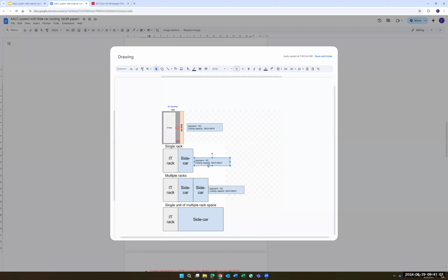After the servers, you will have something more, 5 Kelvin more, something like that. You will have 30 degrees. Basically, if you put approach temperature, you really don't care about the absolute temperature, right? It's important because you are very limited by the temperature of the air of the data center. You cannot put the air at 0 degrees Celsius, but neither at 35 degrees Celsius.